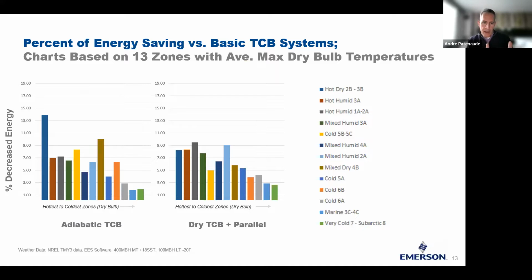So adiabatic alone on the far left. Now what this chart represents is all 13 climate zones listed with adiabatic gas cooler alone. And what that bar represents is a decreased energy relative to a standard booster system with a dry gas cooler. So you can see that the highest ambient zone, which is a hot, dry 2B, 3B, with adiabatic alone gives me almost 14% savings.